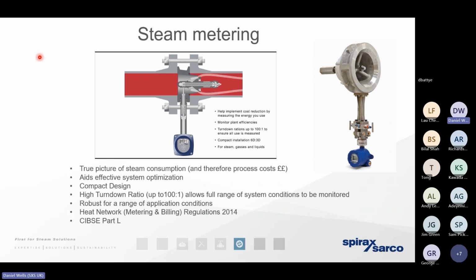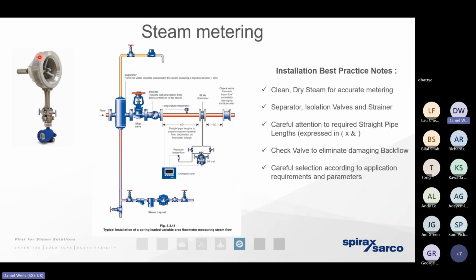For example, if our steam heat exchanger is calling for more and more steam over a period of weeks, that could be that there isn't enough energy in the steam, therefore we need to supply more of the steam. In other words, the steam could simply be wetter. It could mean that the steam is carrying a lot of foam or scale that's creating a barrier to heat exchange. Again, that could tell us that there's something not quite on point with our steam generation. But steam meters, they need to be considered as a number of components rather than one standalone item.